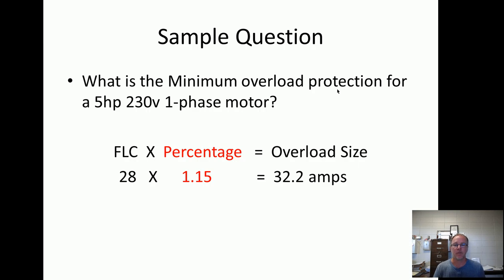Sample question: What is the minimum overload protection for that five-horsepower, 230-volt, single-phase motor? We established the full load current was 28 amps. The question doesn't say anything about service factor or temperature rise, and it does say minimum. So we use the all-other-motors percentage: 28 amps times 1.15 equals 32.2 amps. We need to size an overload at 32.2 amps, or find the next size up closest to that.